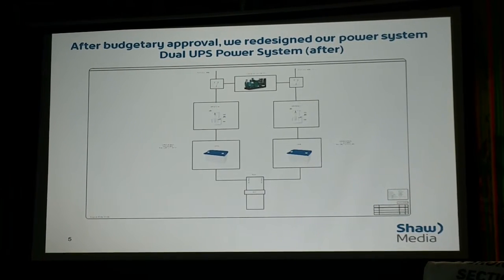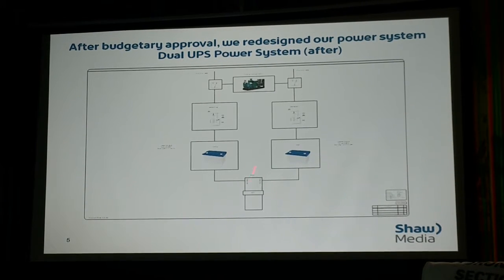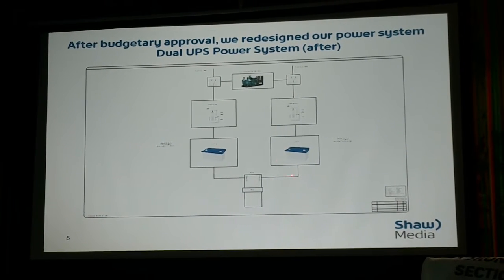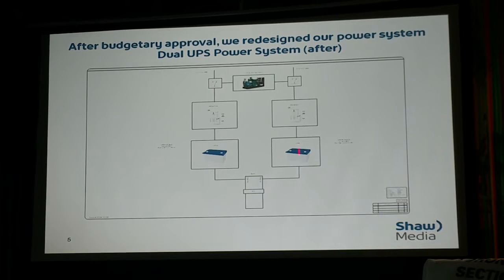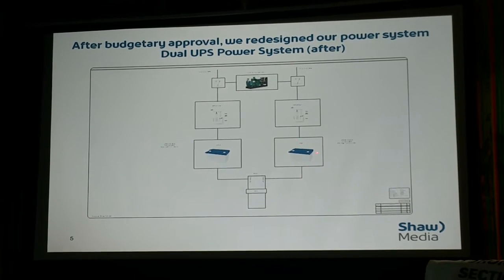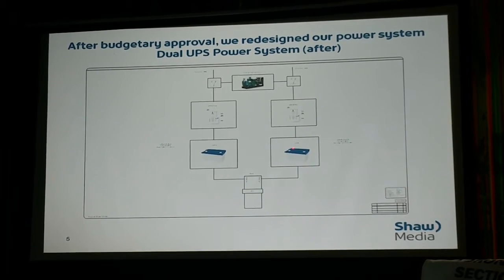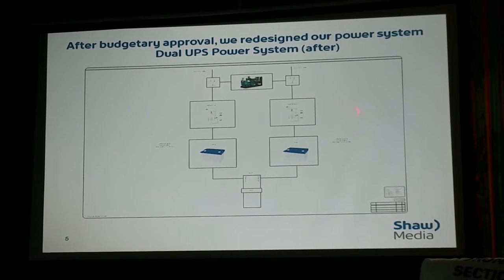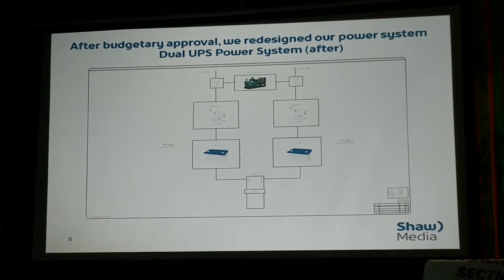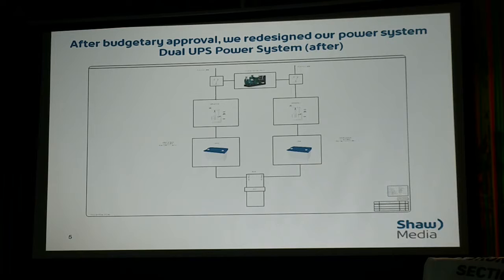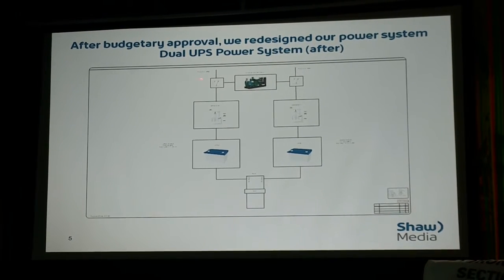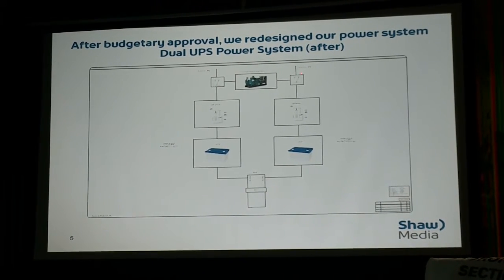The beautiful thing is, in each rack in our facility, we have 2 power bars. Each one feeds a separate UPS, and each UPS can hold the entire load of the system. And then they've got separate breaker panels, just in case we have a failure at the breaker panel level, and separate transfer switches between our diesel generator and our utility power.